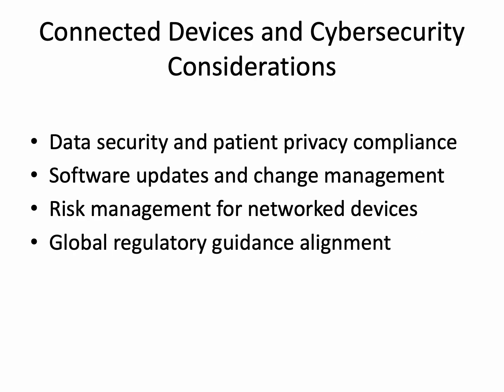Connected devices, including remote monitoring and IoT-enabled equipment, require rigorous cybersecurity and data privacy controls. Manufacturers must establish secure software update procedures, change management protocols, and vulnerability monitoring. Risk management plans should address potential security breaches and ensure continuous device functionality and patient safety.